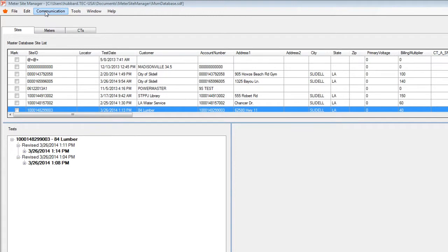At no point after this do you remove or touch the cable or turn off your software, turn off your computer, turn off your Powermaster until you are completely 100% done with your data transfer both ways. Disconnecting the cable, turning off the units, the software can and has caused database corruptions.